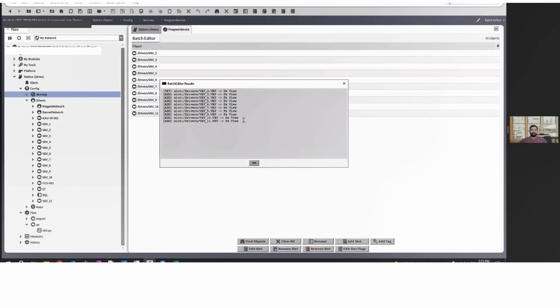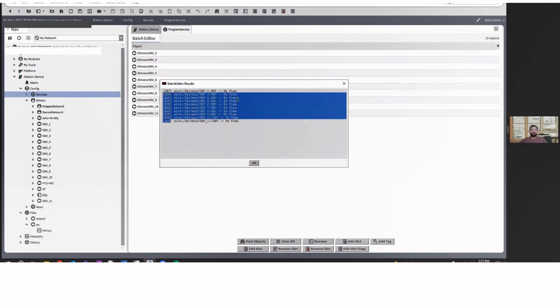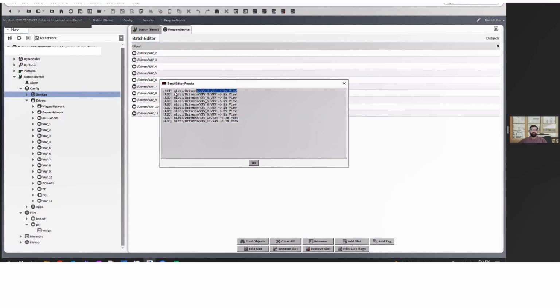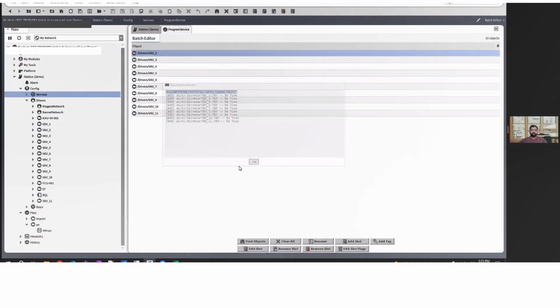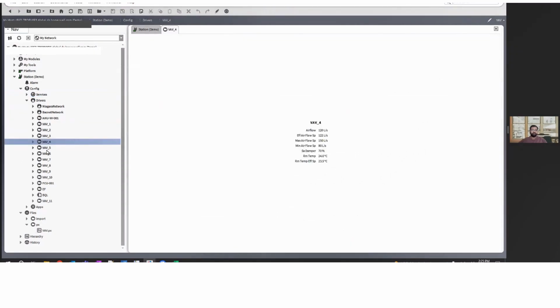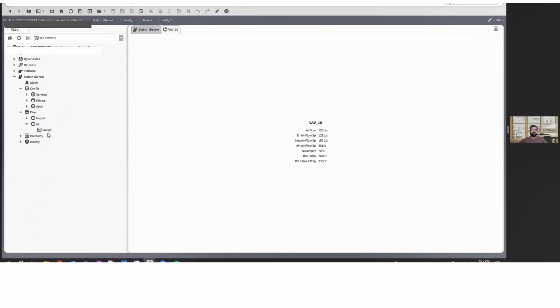If you notice, wherever the PX wasn't assigned, it has added action 'add', and wherever it was already assigned, it has redone it with action 'set'. If I hit OK, you'll notice all the VAVs now have the PX assigned, each with a unique name. This is how you can do your graphics in bulk, just create one PX for all the typicals.